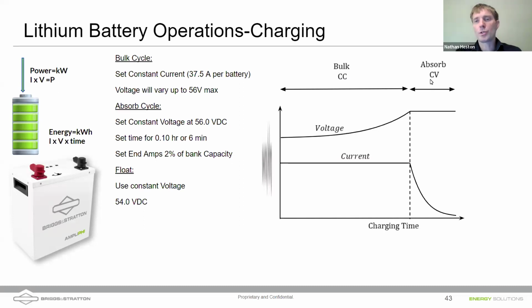So that's the absorb part of the cycle, a constant voltage, so 56 volts for 6 minutes. If you have charging equipment, you can set it to either 0.1 hours or 6 minutes, same amount of time, right? When the battery gets to this absorb cycle, it's already about 90 to 95% charged. A small amount of energy is delivered during the absorb cycle, in which the current drops down. And once that current either reaches 2% of the overall amperage of the battery bank, or we get to a time of 6 minutes, that ends the charging cycle, and we consider our battery 100% charged. It's at least 99% charged at that point. So the bulk is probably about 95% of the charging, another 4 or 5% during the absorb cycle.